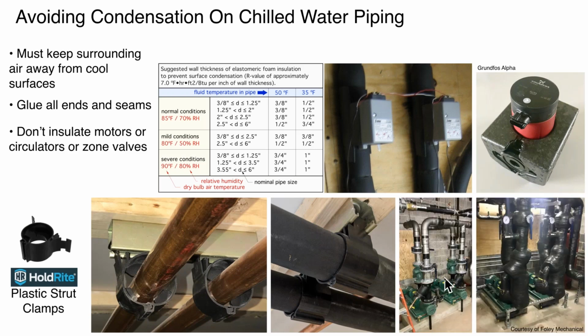Here's another photo. It does show, quite honestly, insulating some of these piping components where you've got some type of anti-vibration separator here. You've got valves involved. You can see the insulation. This is elastomeric foam, wrapped around there. Foam tape has been used to put it together and so forth. Again, it's a necessary part of dealing with chilled water piping, and it's very important to do it correctly.